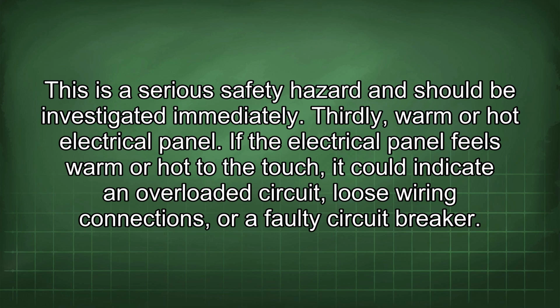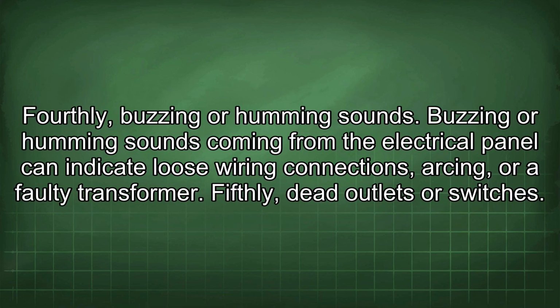Thirdly, warm or hot electrical panel. If the electrical panel feels warm or hot to the touch, it could indicate an overloaded circuit, loose wiring connections, or a faulty circuit breaker. Fourthly, buzzing or humming sounds. Buzzing or humming sounds coming from the electrical panel can indicate loose wiring connections, arcing, or a faulty transformer.